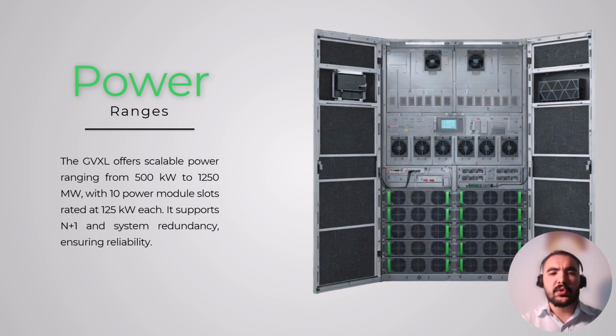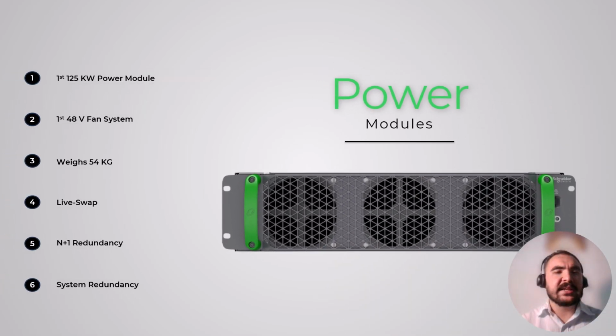This image shows you the UPS frame. Now, the UPS frame provides 10 available spots for power modules. Each of these power modules is rated at 125 kilowatt of power. And this is the first power module by Schneider to be rated at 125 kilowatt of power, with the first 48 volt fan system. All of the previous fans were at 24 volt. Each power module weighs around 54 kgs, so you need 2 strong men to carry the power module.